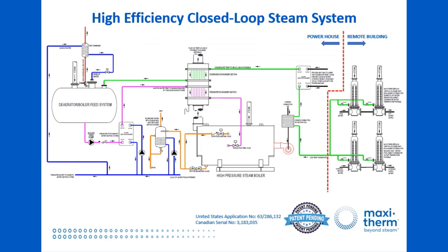Here is a recap of our high-efficiency closed-loop steam system, now showing how MaxiTherm vertical flooded heat exchangers can provide sub-cooled, low-temperature condensate back to the main steam boiler plant. This is a typical system showing MaxiTherm's producing hydronic heating water as well as domestic hot water. Modern buildings designed to use and return low-temperature water — for example, to maximize the efficiency of a condensing hydronic boiler — offer the perfect process temperature ranges that allow MaxiTherm to produce the cool condensate necessary to achieve 95% overall efficiency in our steam boiler plant. So you don't have to imagine a high-efficiency steam system — now you know it's a reality.